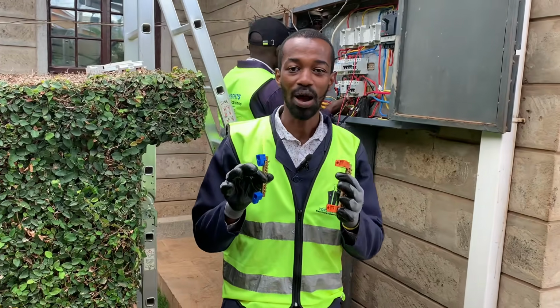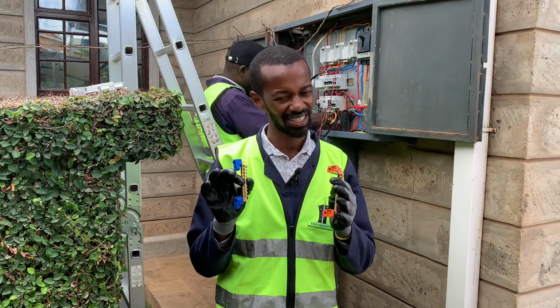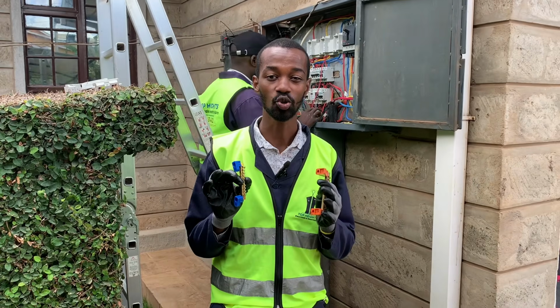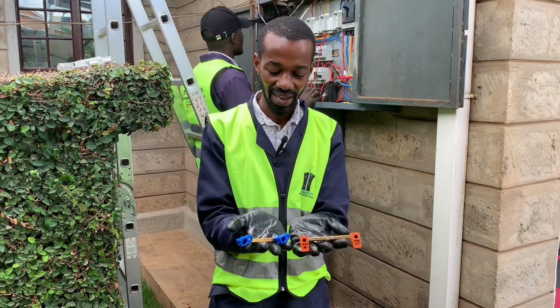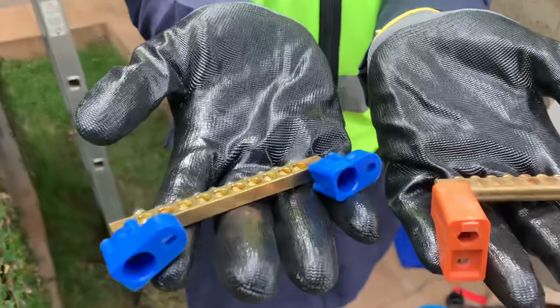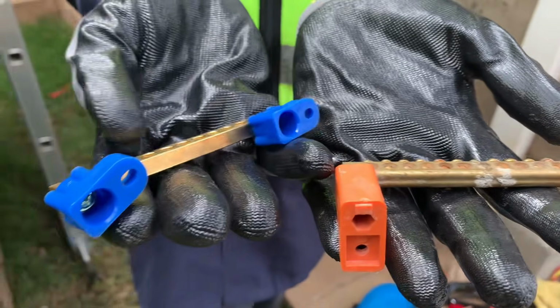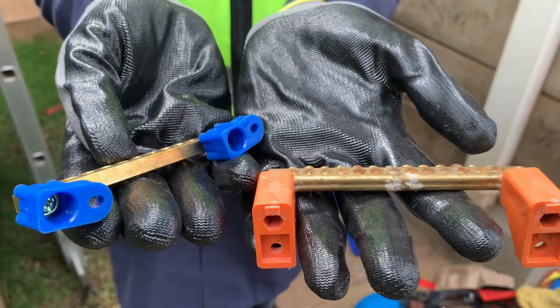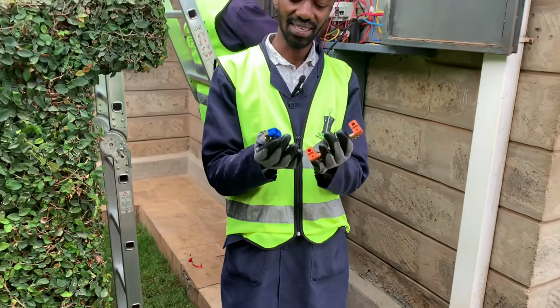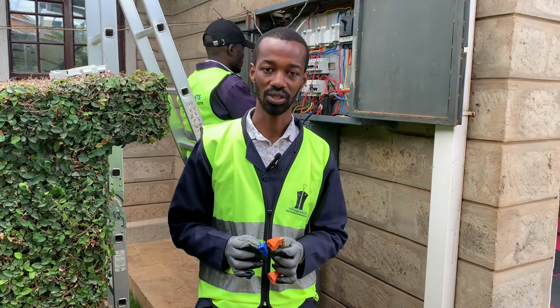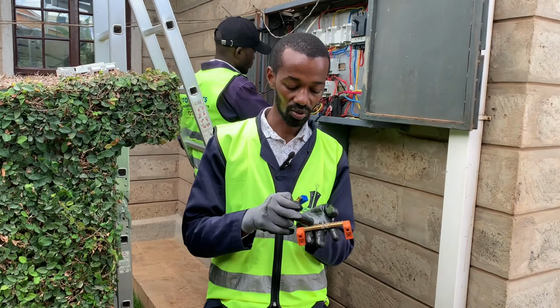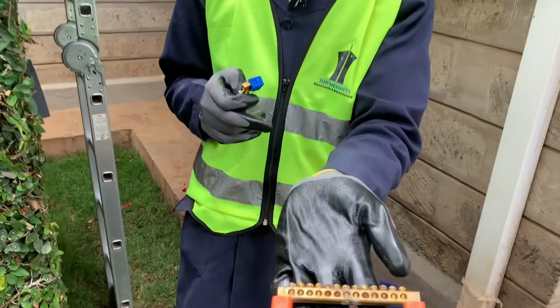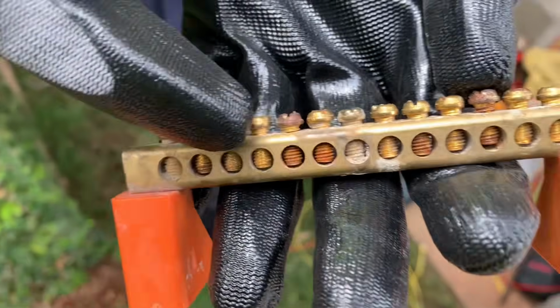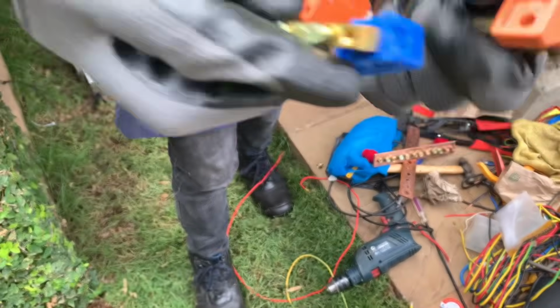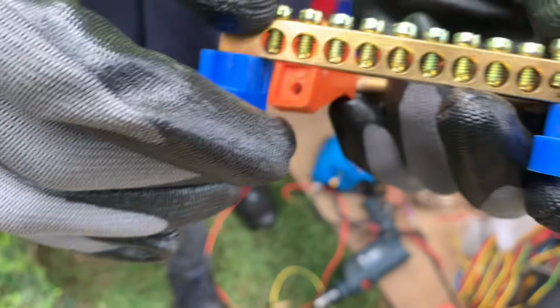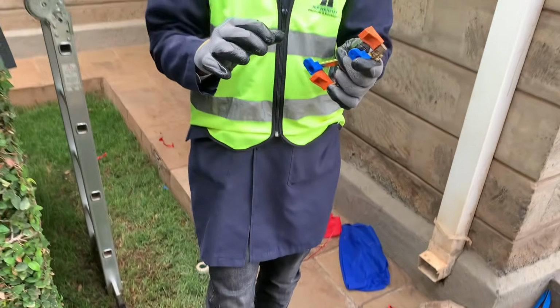Now, I want to talk to you about something that is very important and means a lot when it comes to electrical installation. In my hands, I have two bars. This is a neutral bar. You can connect a neutral connection here, or you can connect an earth connection. These bars are used in the consumer unit. They are very small. We replaced this one because it was really rusting, as you can see from this point here as well as here. So we are replacing it with this. You can see it is pure copper so that it will not compromise on the connection.